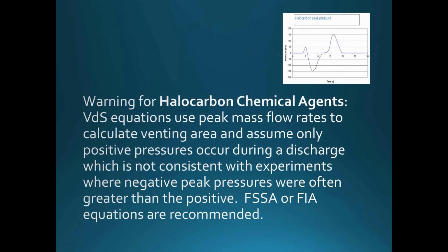I know that we've had several people get hold of us and say, oh gee, how come the VdS equations are specifying such a small vent? And our response is, well, I've not ever seen experimental results that match the ones that they give, so I would tend to favor what I've actually witnessed with my own eyes, which are the FSSA or FIA equations for halocarbon agents.